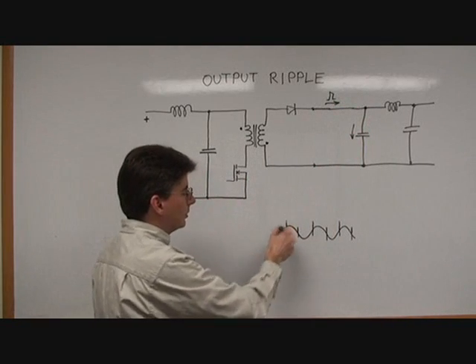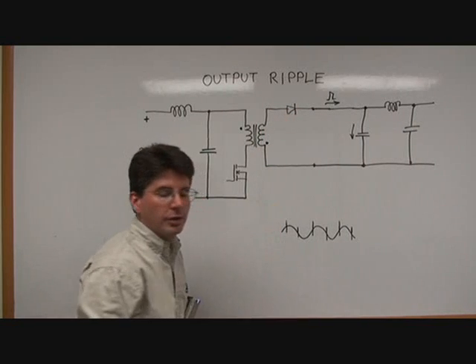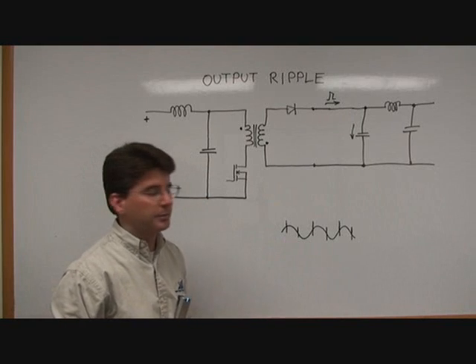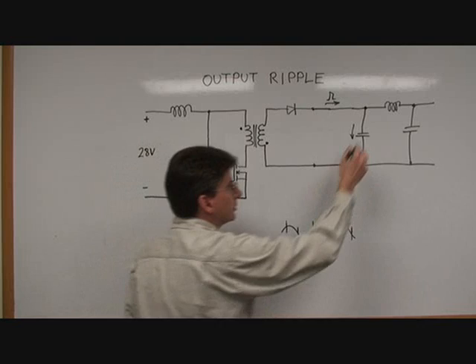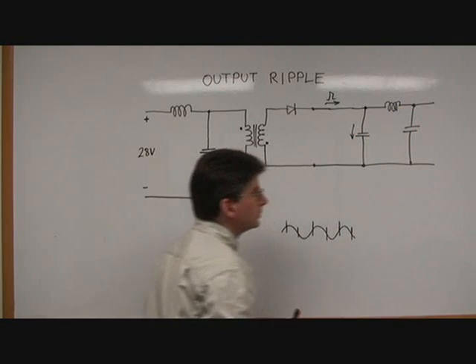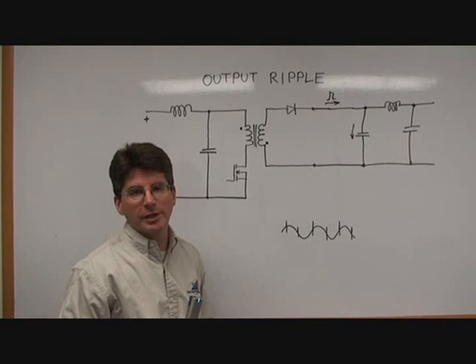It will include a sinusoidal component which is due to this current flowing in this capacitor. It will also include some higher frequency switching spikes due to switching events occurring on the diodes and rectifiers. All this needs to be filtered and is filtered by this LC here.